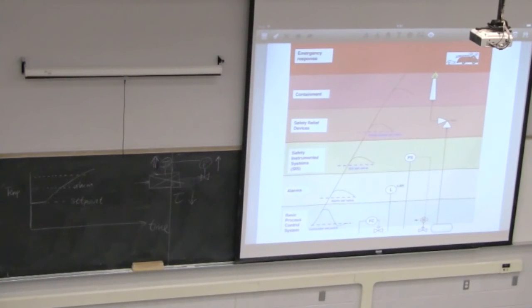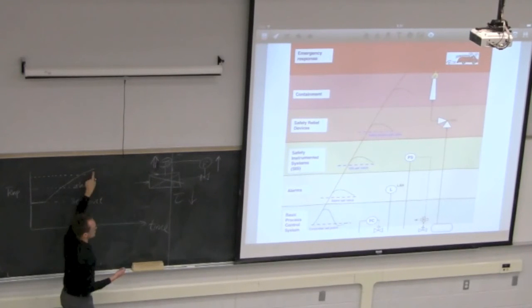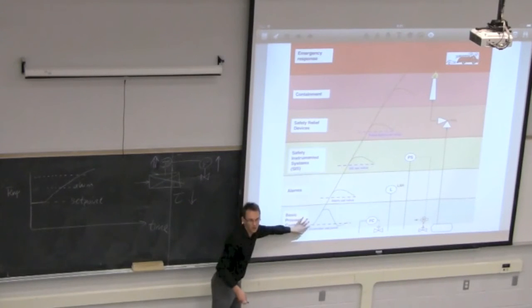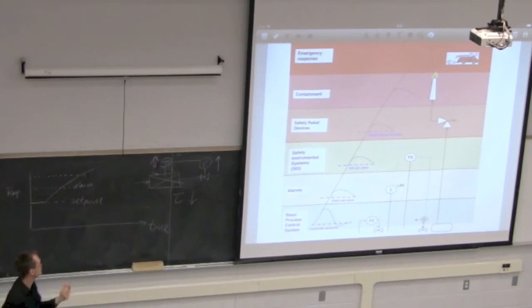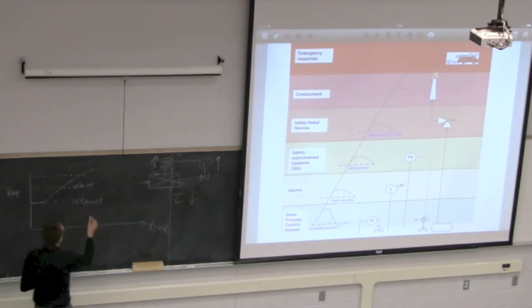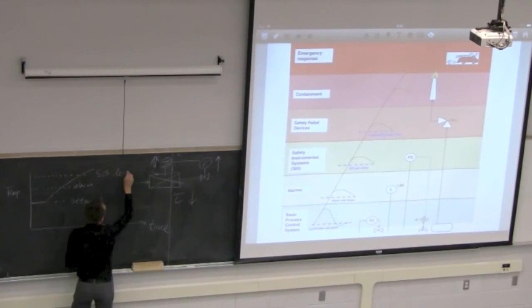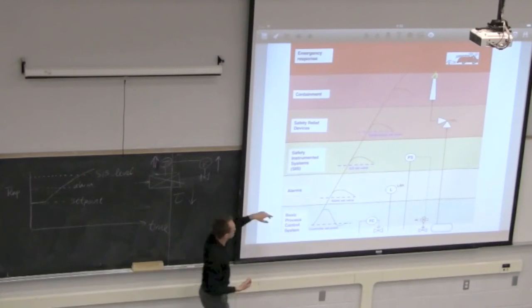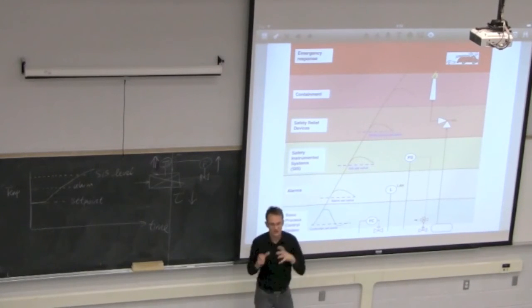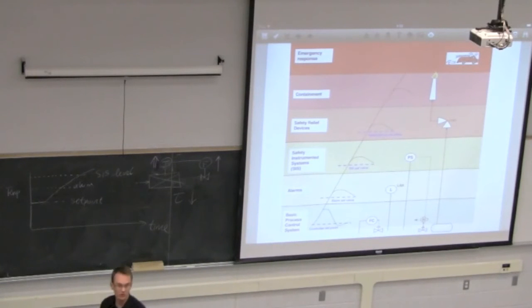Right? So we don't want to suffer that economic loss because someone is not able to control the temperature, or because this lower level here fails. Right? So we don't want to incur economic costs or safety issues due to that. So we have then our SIS level, or our high level alarm in this case. That may kick in, and it will be a mechanism, we'll learn more about it, that will shut this process down without human intervention. It will automatically bring the process to a safe point of operation.